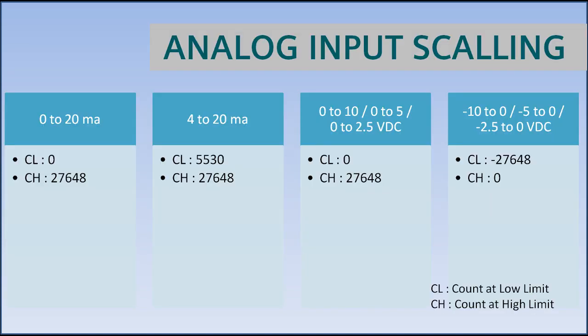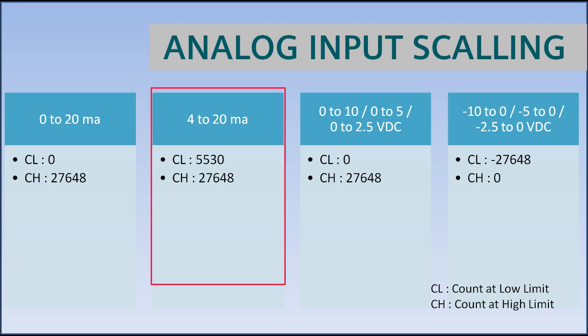This table shows the input count based on your input type. For example, say you are having 4 to 20 milliamps input signal. So your input count will be between 5530 at 4 milliamps and 27648 at 20 milliamps.